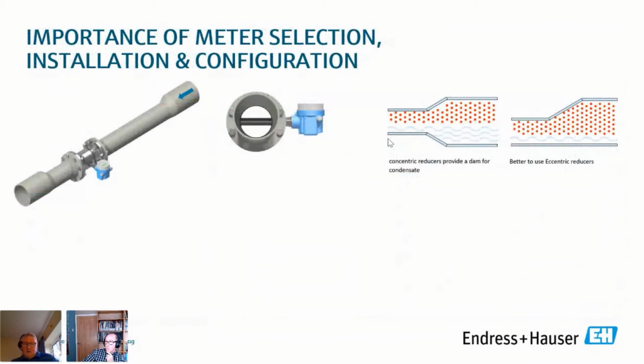And I just mentioned about having the right units. The other thing on the steam line is that the meter's installed properly. So here we've got a meter, and most steam meters are velocity sensitive, which usually means we reduce the line in order to get better turn down from that technology. In just reducing the line using concentric reducers here, we'd create a dam for the condensate if it was to build up. This is the last thing we want, because it will cause water hammer, it'll affect the measurement, and it'll actually do damage to the line.